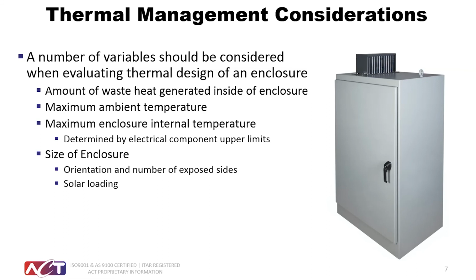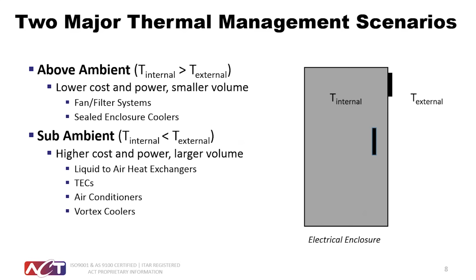The physical attributes of the enclosure, such as size, construction material, and location relative to other enclosures, is important as well. There are two major thermal management scenarios, commonly referred to as above ambient and sub-ambient cooling. If the enclosure internal temperature is higher than the temperature outside of the enclosure, it is considered above ambient. Fan filter systems and sealed enclosure coolers are two examples of above ambient cooling products.